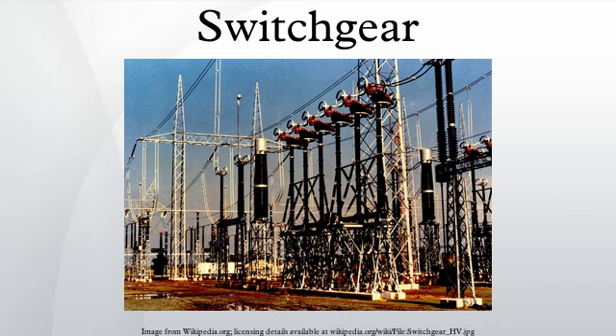Functions: one of the basic functions of switchgear is protection, which is interruption of short-circuit and overload fault currents while maintaining service to unaffected circuits. Switchgear also provides isolation of circuits from power supplies. Switchgear is also used to enhance system availability by allowing more than one source to feed a load.